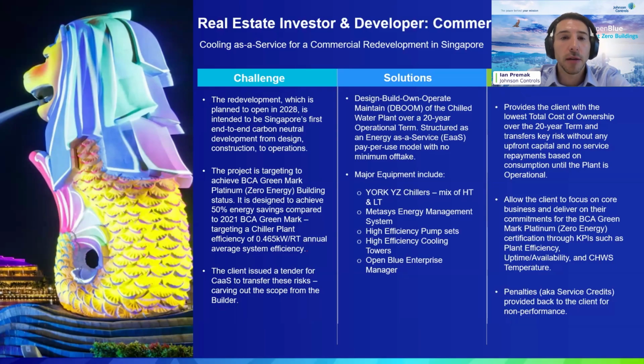What we ended up providing was a 20-year energy as a service structure, specifically cooling as a service, where we're providing chilled water as that utility. We as Johnson Controls are the OEM of the chillers and the BMS, and we also have our digital platform called OpenBlue. We're using third-party materials like pumps and cooling towers to complete the system, and we're doing the full design, build, operation, and maintenance of it.